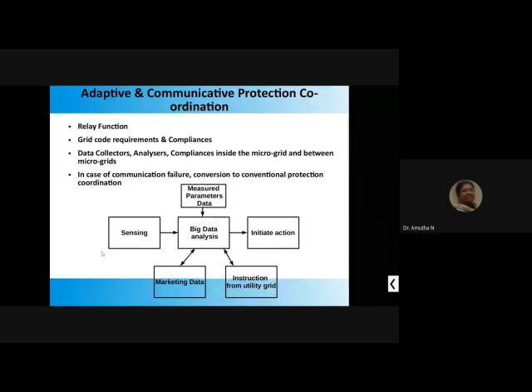So whenever microgrid penetration increases, the protection coordination becomes adaptive and communicative. It is adaptive because it has to adapt to the grid code requirements as well as the relay characteristics. But what is communicative? It's communicative because the relay is going to communicate with the nearby microgrids also.